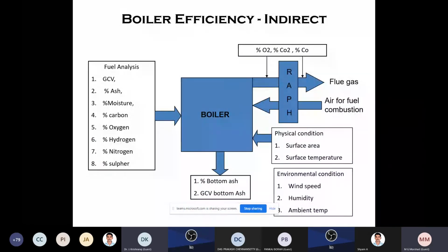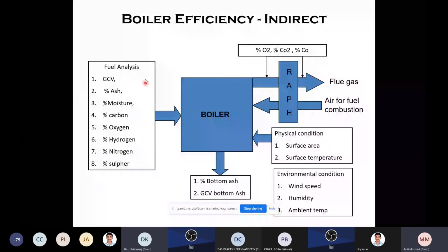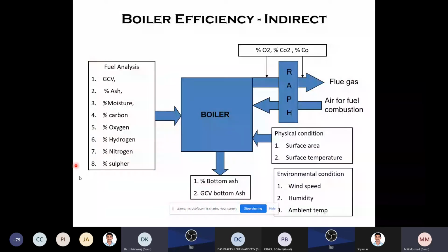Now, boiler efficiency by the indirect method. The indirect method is a very descriptive method. You have to get so many data from the local DCS, and the fuel analysis is available, and with that you can calculate all these things. So what data do you have to get? First, the fuel analysis data: GCV, ash, moisture, carbon, oxygen, hydrogen, nitrogen, sulfur. These are the fuel analysis data you have to get from the laboratory. They will carry out the analysis and give it to you first. It will also be available in the shift engineer data sheet, the every day's data sheet.